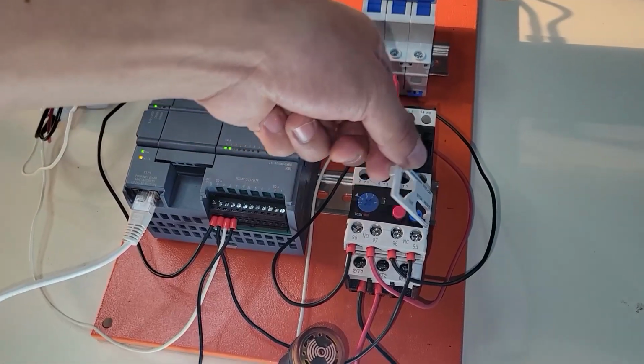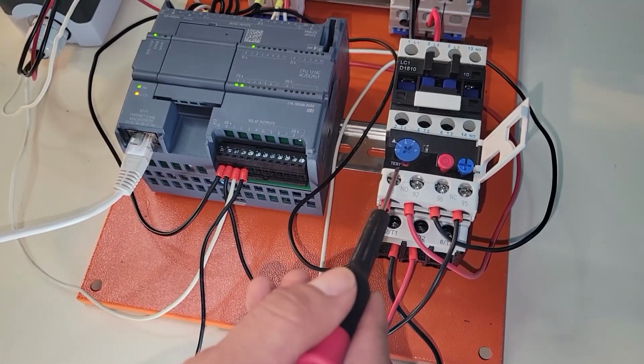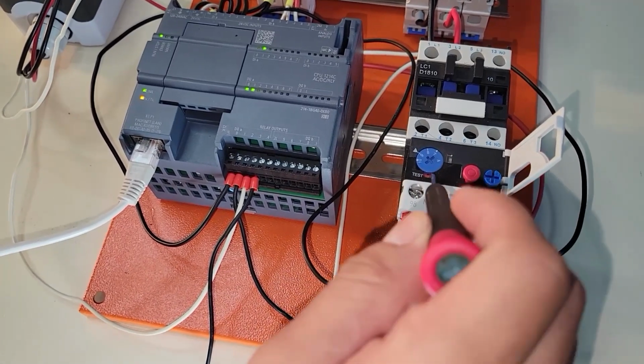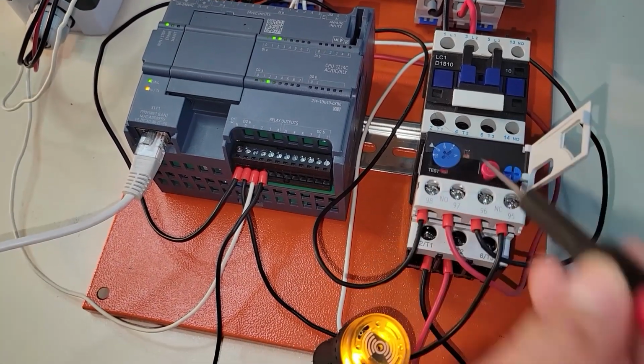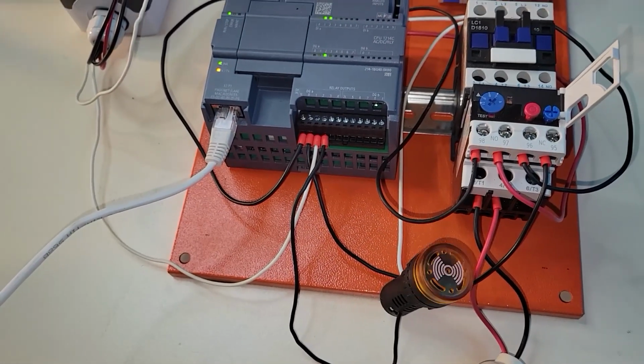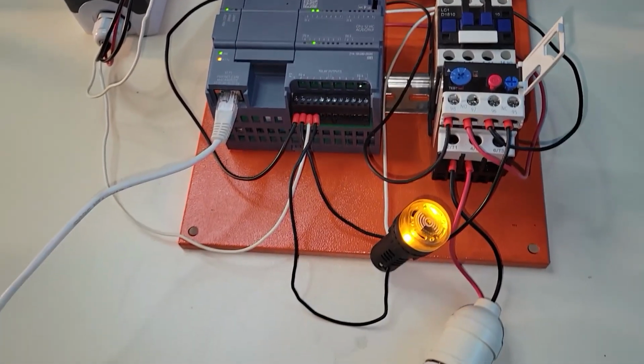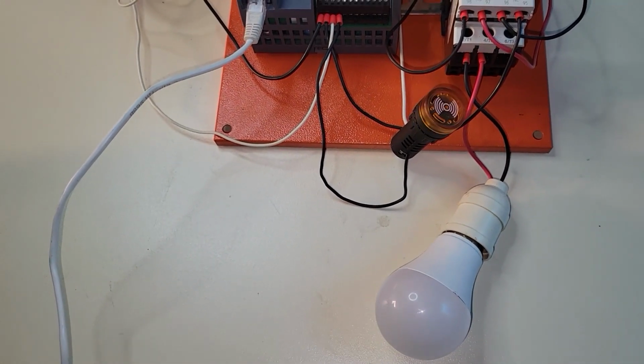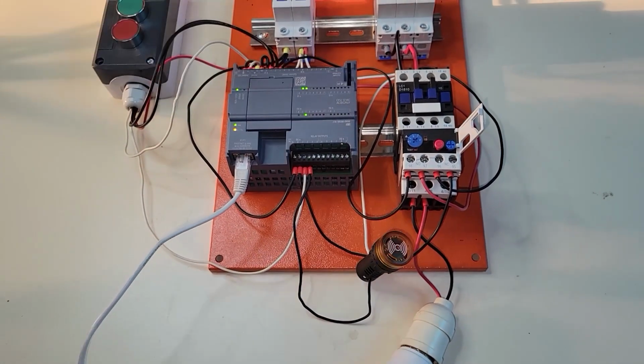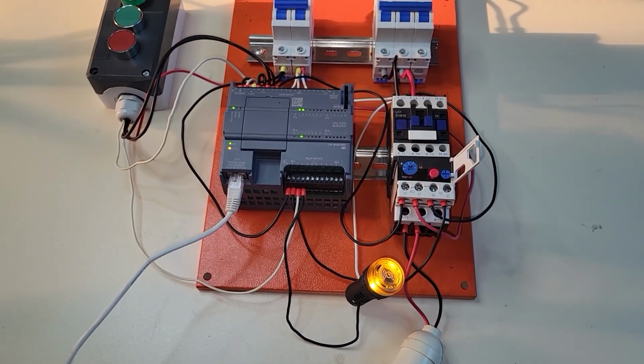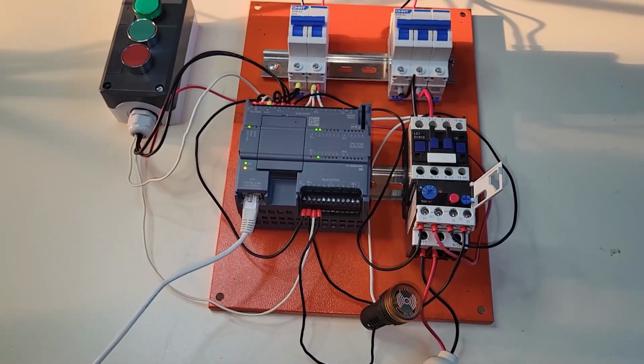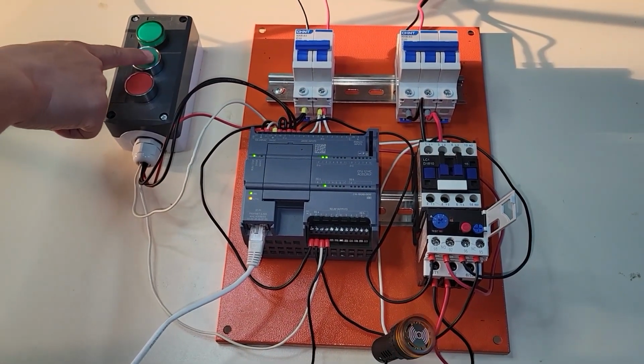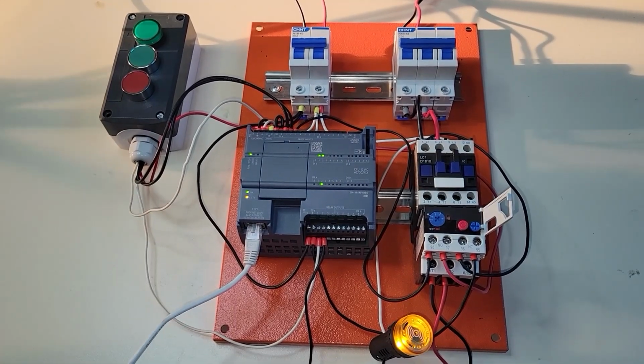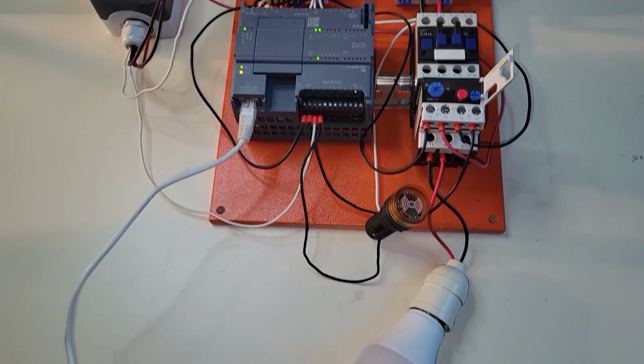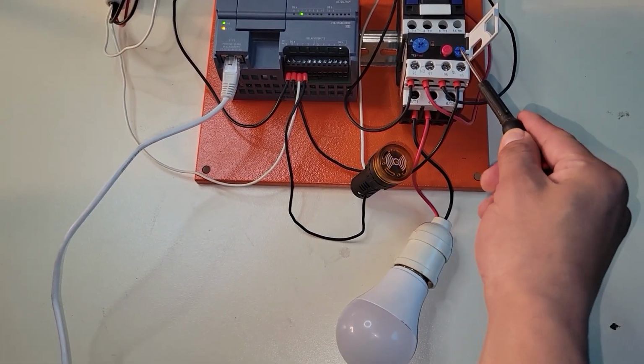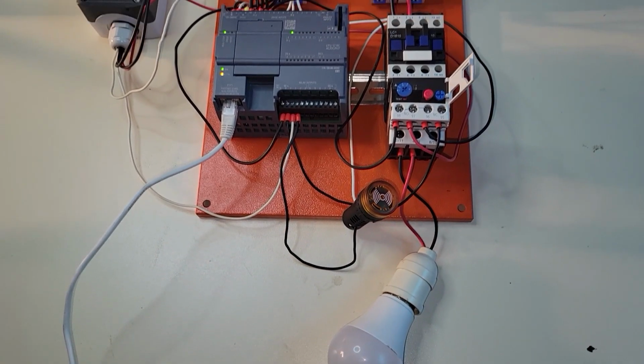Now we are going to simulate that there is a fault due to overload in the motor. So we press the test button on the thermal relay. As we can see in here, the fault indicator light is activated and the contactor automatically opens and disconnects the light or motor to protect it. Then, even if we press the start button to turn the light back on, this will not be possible because the thermal relay is faulty. What we would have to do is check the motor and repair the fault and then reset the thermal relay by pressing the reset button.